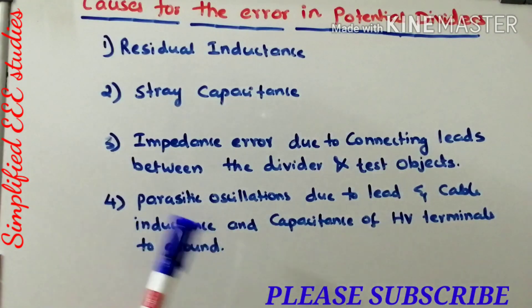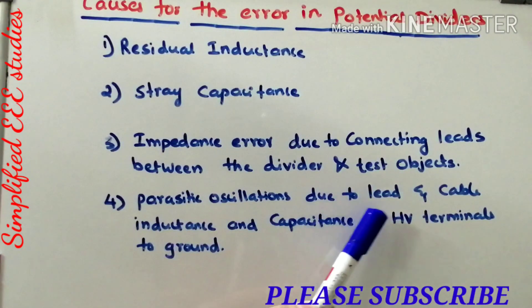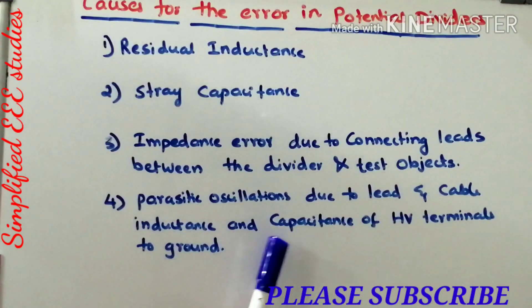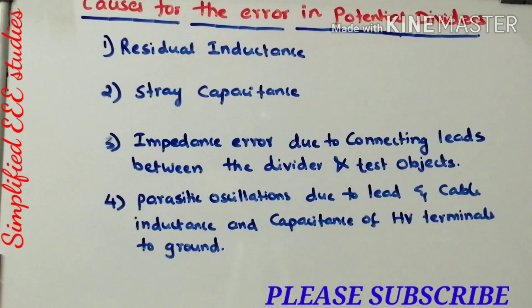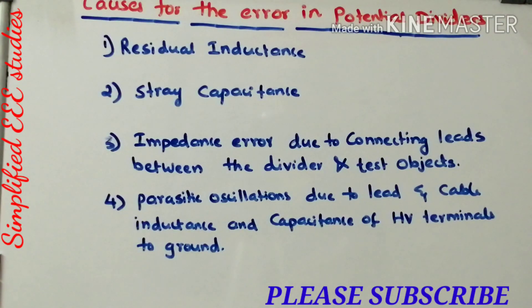The fourth reason is parasitic oscillations due to lead and cable inductance and capacitance of HV terminals to ground. These parasitic oscillations — a sort of vibration — will be causing errors in the case of potential divider measurement. These are the four major reasons which will be causing errors in potential divider measurement. While doing design or calibration, you need to take care of those four errors.